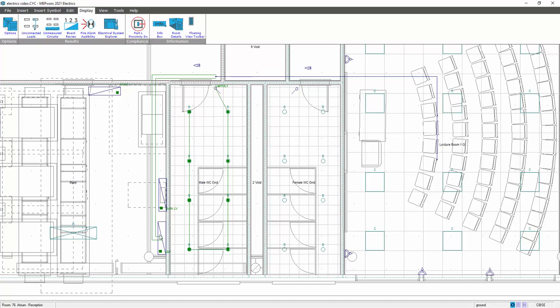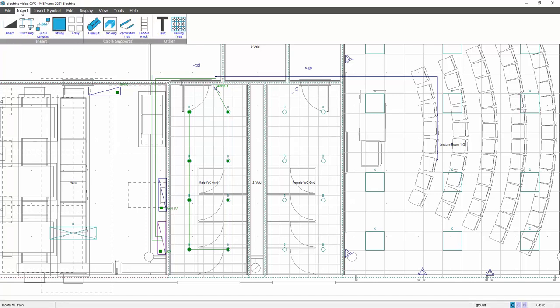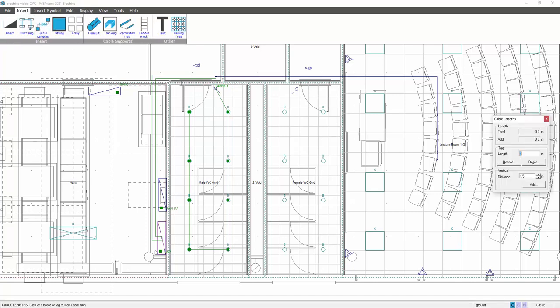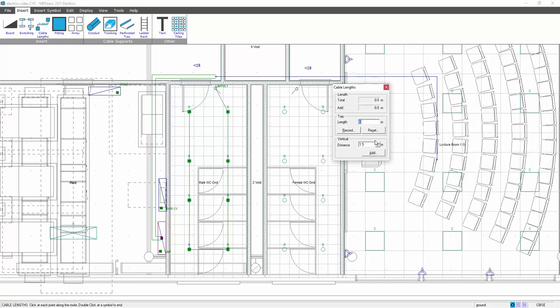So now I'm going to add a circuit from the lighting and power board to the light switch via the movement sensor because it might well be associated with this circuit. So what I do, I select the board. I then insert cable lengths. I select my board, and then on the cable lengths dialog box, I put in the vertical distance off the board. Now I can top these up at the end if I want to. So when we complete the circuit, it'll give us the circuit length in the room and the cable length, and we can adjust those as well.